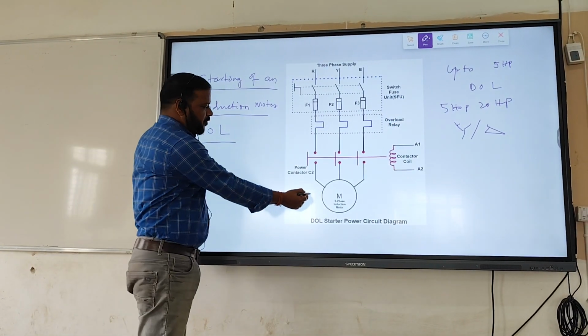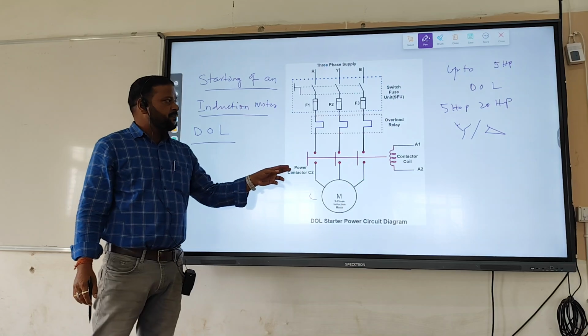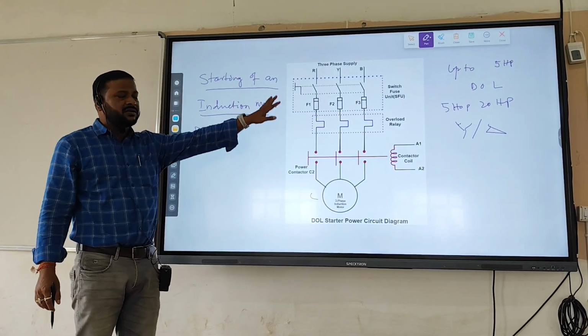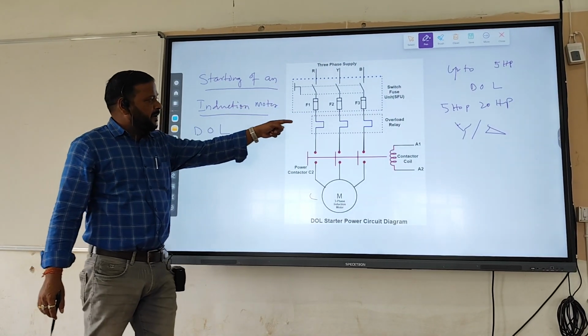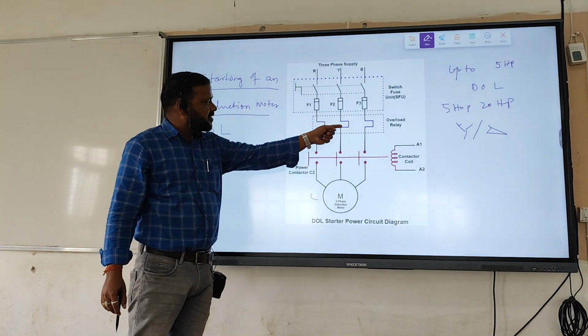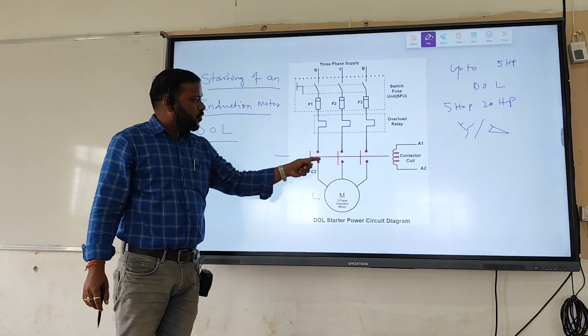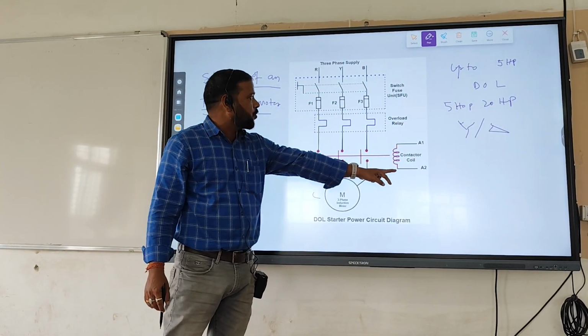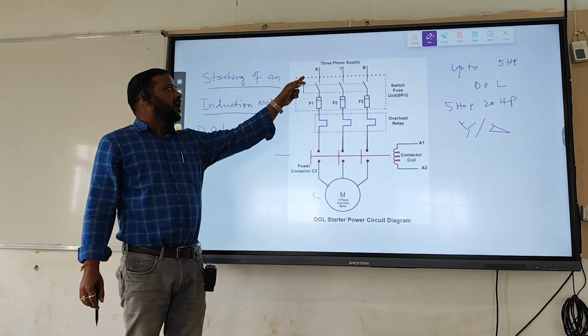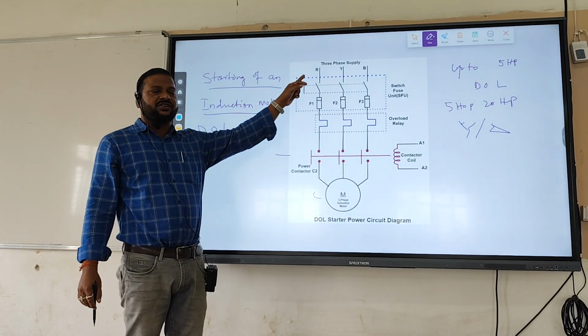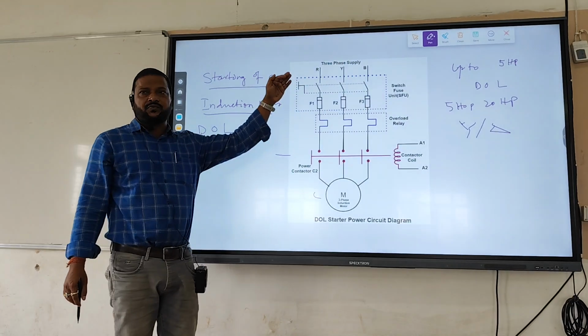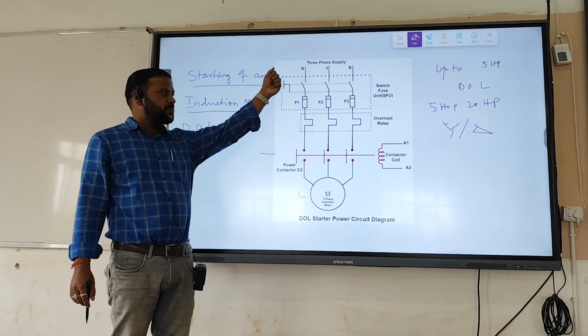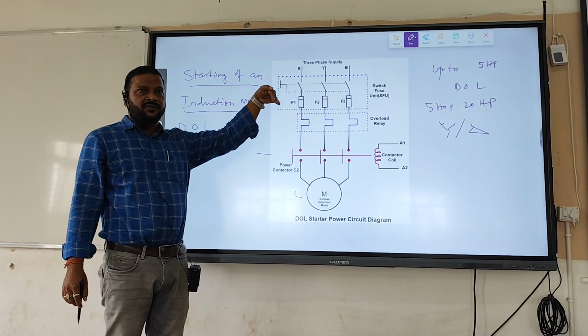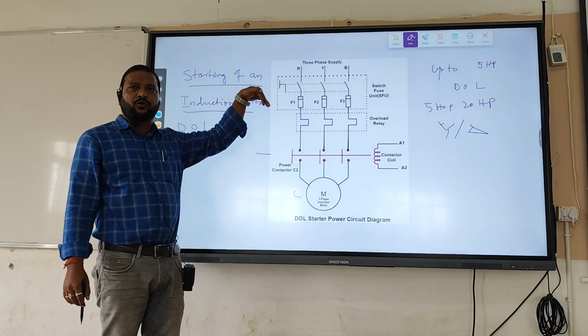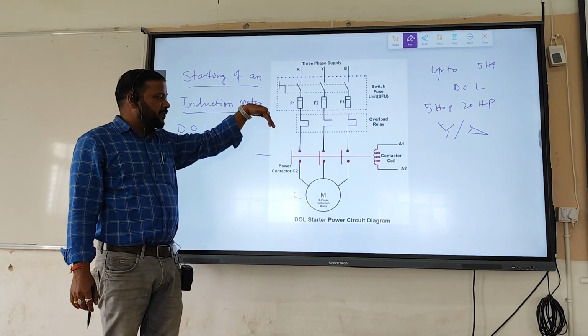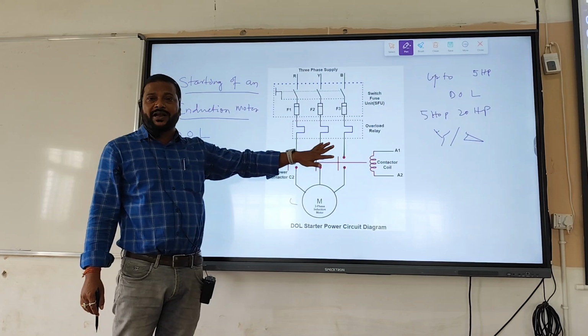So this is our motor, which has 3 terminals, and this is the power circuit of the starter, where you can find the overloads. All these 3 are the overloads, and this is the contactor. This part is the contactor coil. 3 fuses are there, and one TPSP switch. When we give our command to the TPSP, supply comes through the fuse, through the overload relay, then to the contactor.